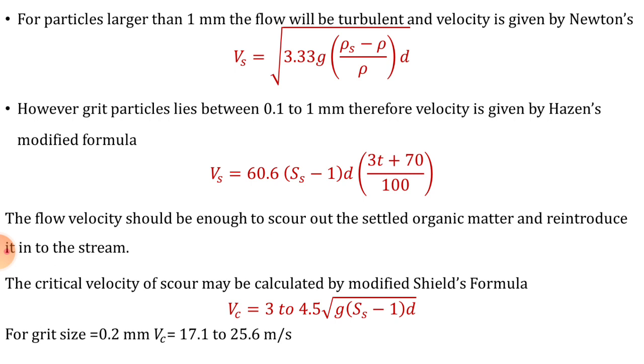The flow velocity should be sufficient to scour out settled organic matter and reintroduce it into the stream. The critical velocity of scour may be calculated by the modified Shield's formula: Vc = 3 to 4.5 × √(G × (Ss − 1) × D), where the constant ranges from 3 to 4.5. For grit size of 0.2 mm, the critical velocity Vc will be 17.1 to 25.6 cm/s.